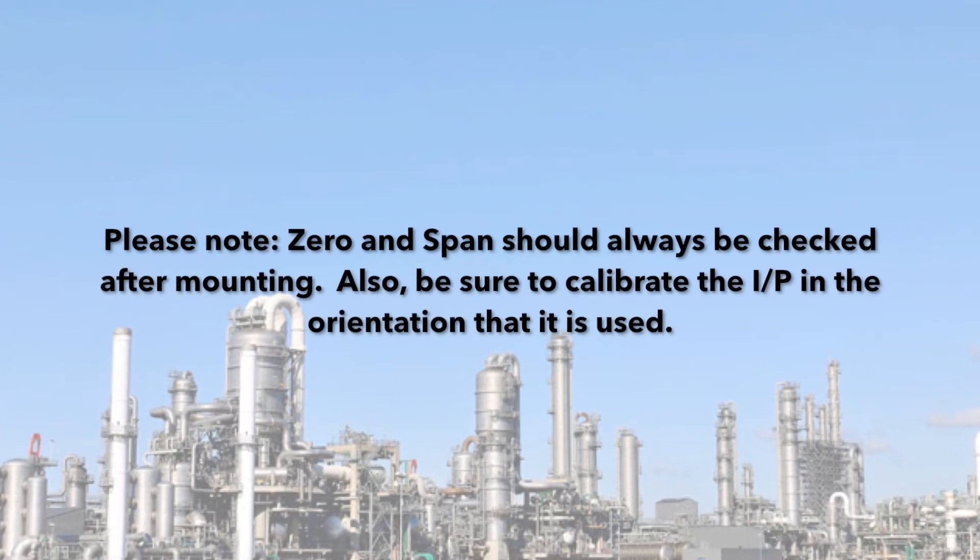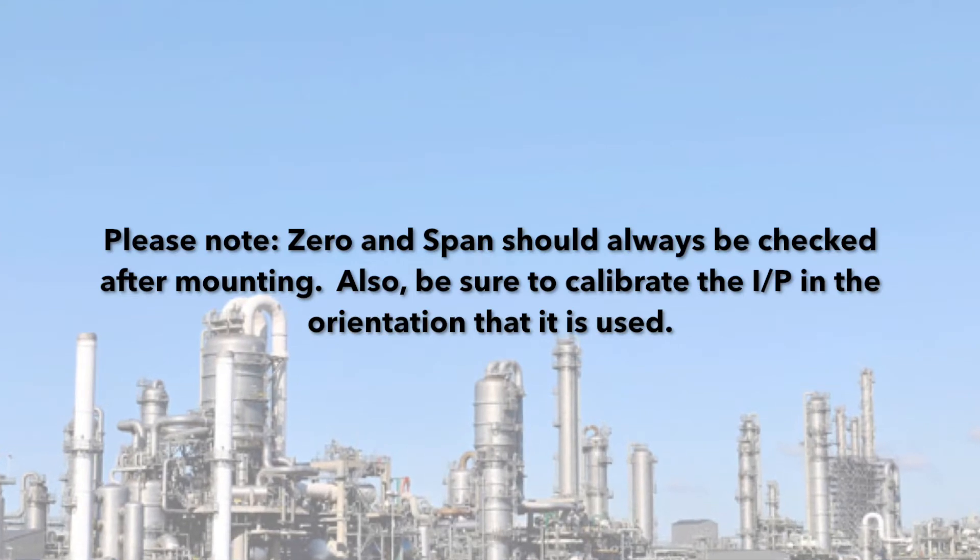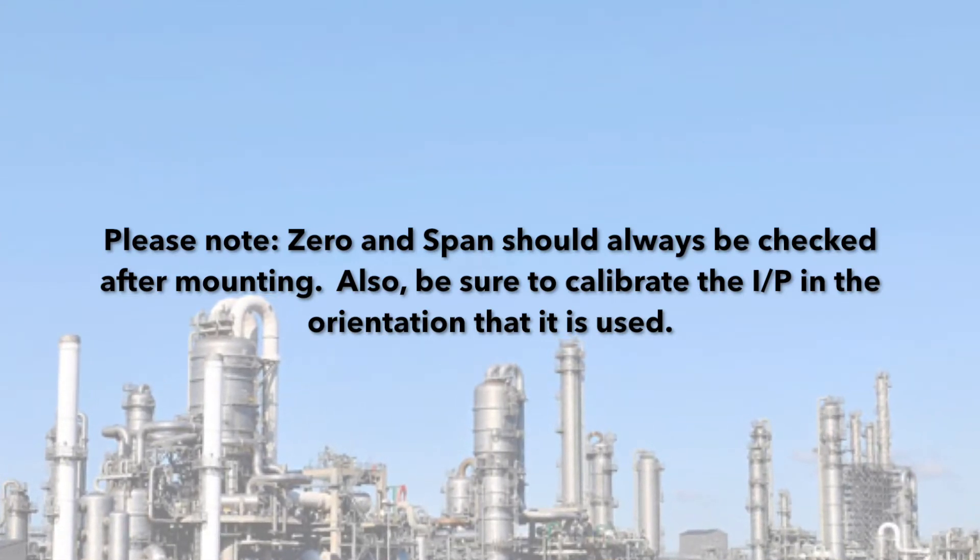Please note: zero and span should always be checked after mounting. Also, be sure to calibrate the I/P in the orientation that it is used.